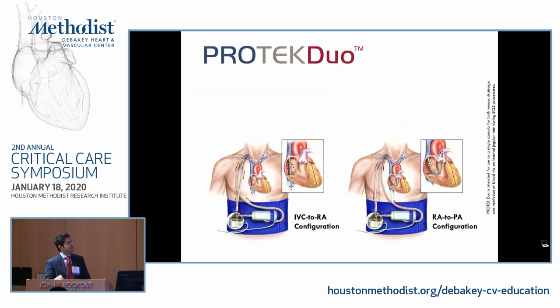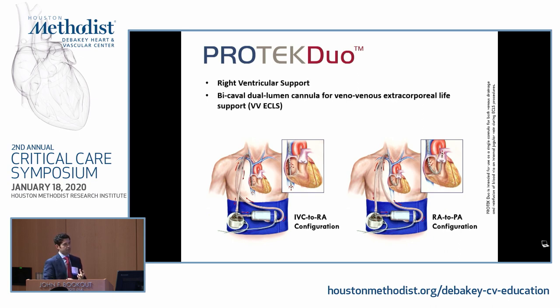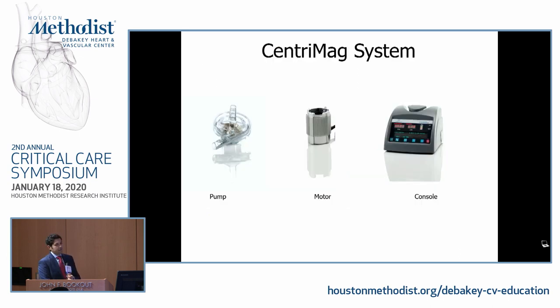The Protek Duo uses the same pump platform but with a bicaval dual-lumen cannula placed in the right internal jugular vein, primarily for right ventricular support. It has two lumens — the inlet sits in the right atrium and the outlet sits in the pulmonary artery — taking blood from the right atrium and delivering it to the pulmonary artery. An oxygenator can also be attached, allowing it to function as a veno-venous ECMO.